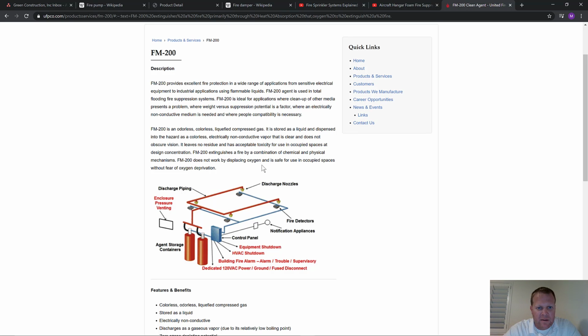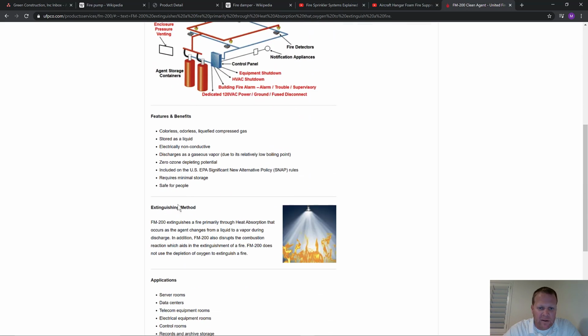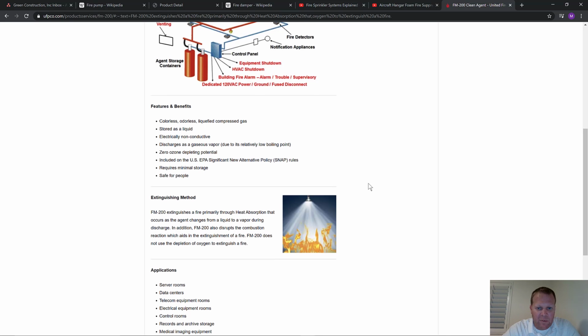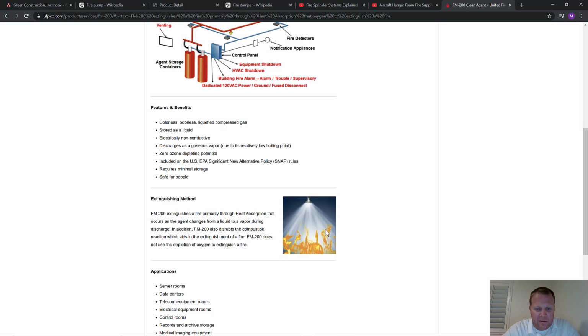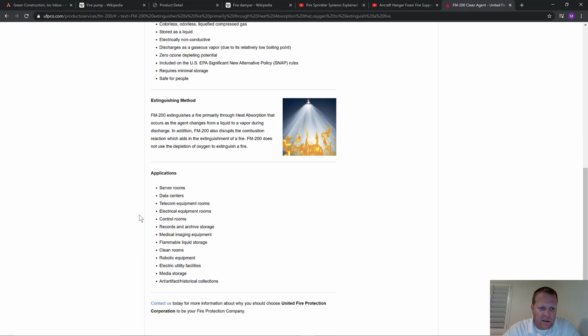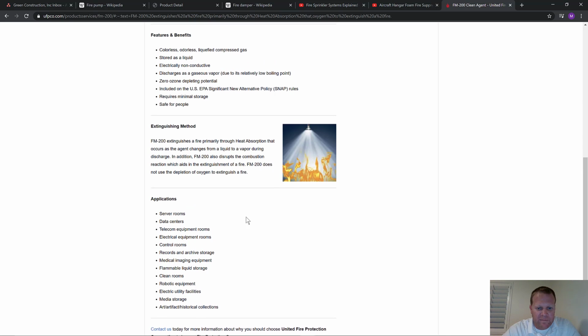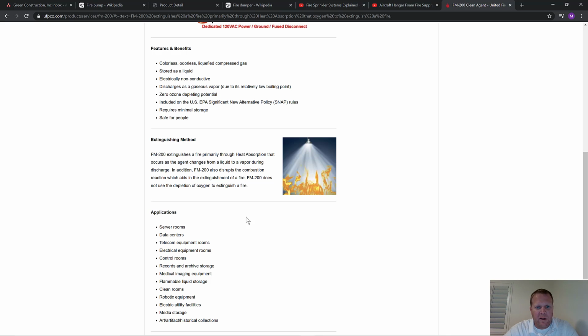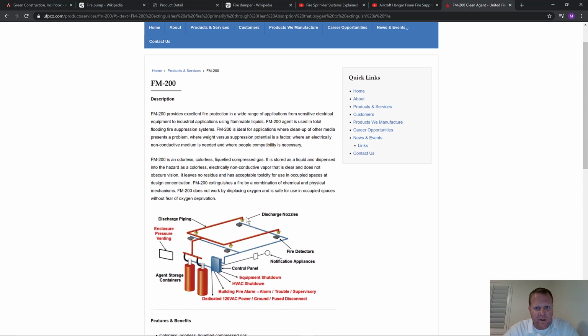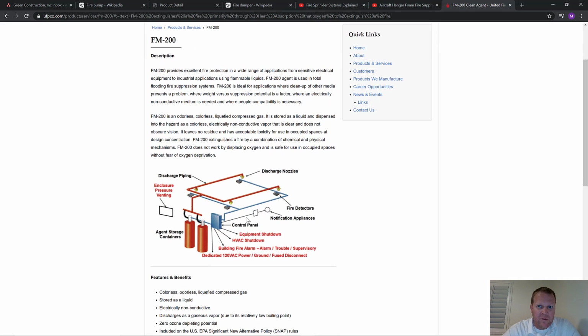Anyway, what I understand very little about here, the extinguishing method, is saying that FM200 extinguishes a fire primarily through heat absorption that occurs as the agent changes from a liquid to a vapor during discharge. So it's cooling this space rather than removing the oxygen. Why would that be important? Because there might be people in there. You remove all the oxygen, and somebody's going to die, or get really hurt, pass out, not be able to leave. And they list server rooms, data centers, stuff like that, where this would be the right way to go about it. I've seen FM200 quite a bit used, so I thought it'd be a worthwhile thing, just to give you a couple little things there.